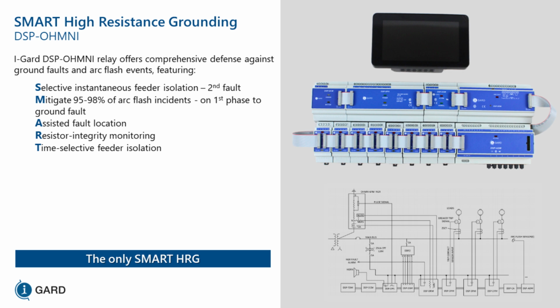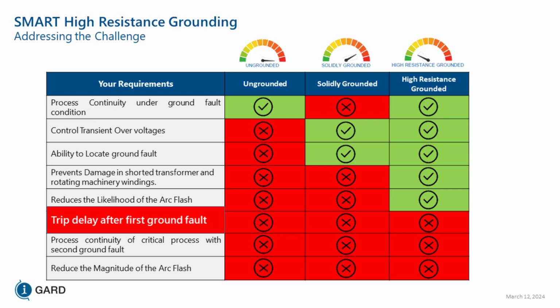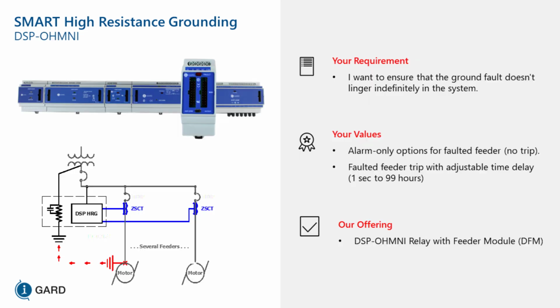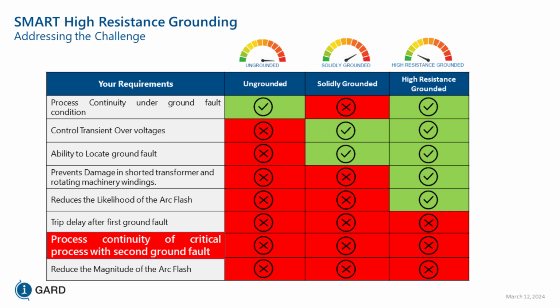And I've located ground faults in facilities that I've never been in before in less than an hour. Any size facility with this type of a system, I can find the ground fault in less than an hour. So, trip delay after first ground fault. That's one of the benefits we got from the smart HRG system. You can program the feeder modules to trip on the first fault after a time delay. Process continuity of critical process with second fault.